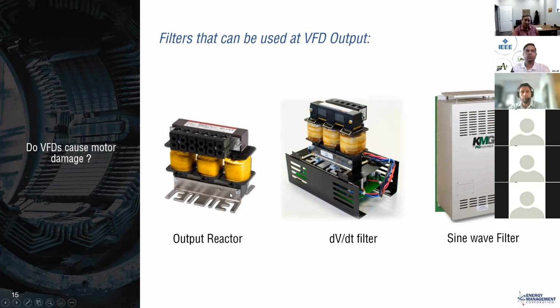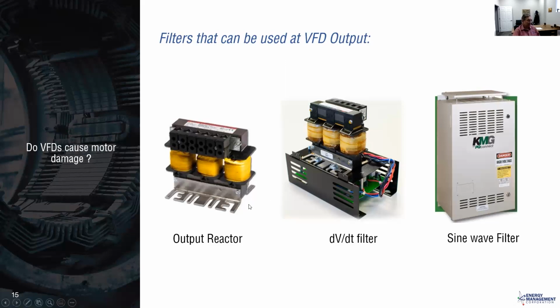But years ago, we ran 1,000 feet of conductor around our warehouse and the offices, trying to measure some of this effect. And we saw in some situations where a reactor itself actually increased that dV/dt. Again, it's an impedance mismatch.